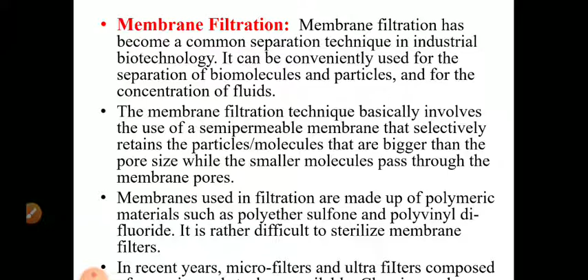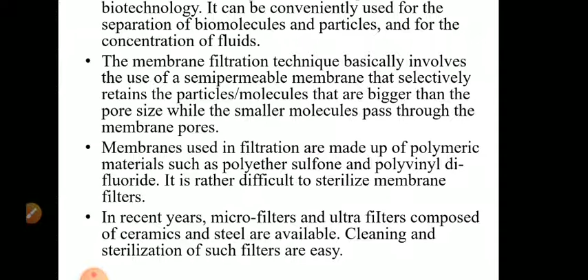Membranes which are used in filtration are made up of polymeric materials like polyether sulfone and polyvinyl difluoride. Now, it is difficult to sterilize these membrane filters. Every time we perform filtration, we require sterilized membrane filters, so they are difficult to sterilize. So in recent years, microfilters and ultrafilters composed of ceramics and steel are available, and cleaning and sterilization of such filters is easy.